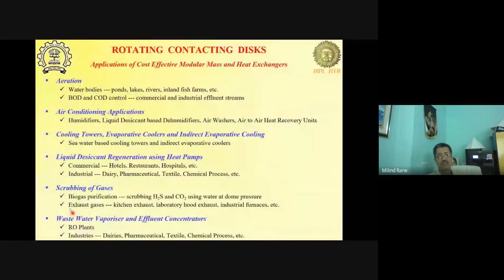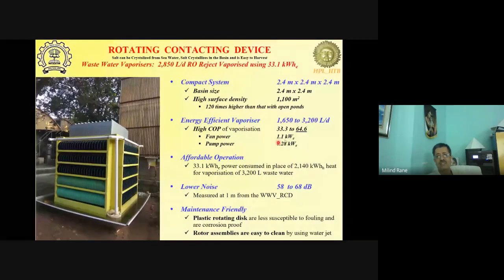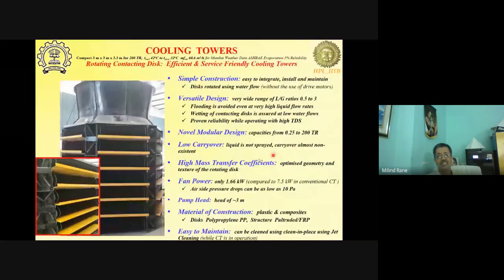This can be used for kitchen hood exhaust cleaning and all those things. The power consumption of the fan and all those things can come down significantly. So as I said here, you can see the COP is 64.6, as high as this in this case example. And then these are the 200-ton cooling tower that we have deployed. And the best part is our power consumption in this case. Now our latest power consumption is 1.5 kilowatt as compared to conventional 200-ton deployed with 7.5 kilowatt of power input.